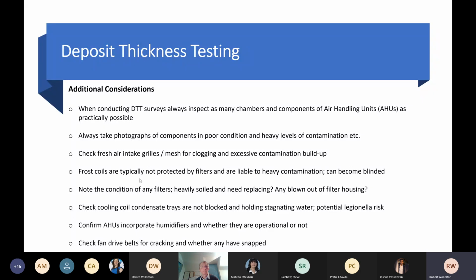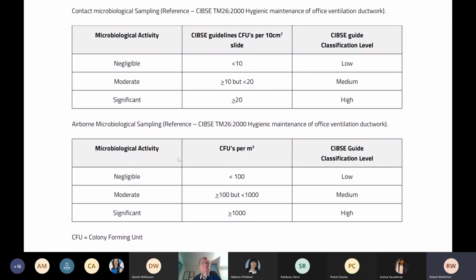Frost coils within air handling units can have a great impact on affecting the flow rates within the system if they become contaminated and blocked. Filters, I'll come onto that later on. And then various other things, checking fan belts, which should be part of the general maintenance anyway.